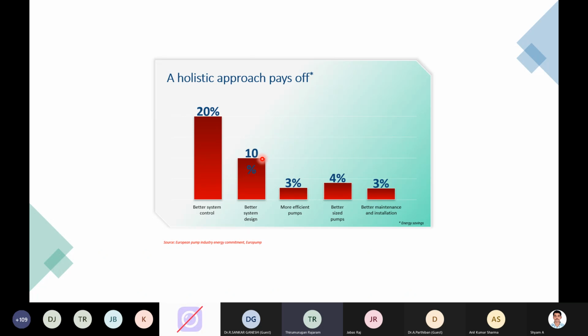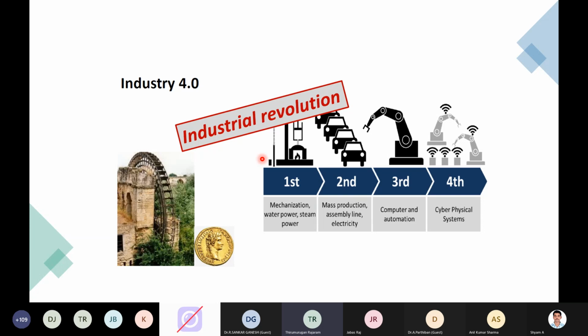So whether you want 4 bar pressure in your line, the pressure transmitter will always sense that and give a signal to the pump so that the scenario will always be maintained. The same thing, if you want a delta T of 5 degrees in your cooling tower, you can have a temperature sensor and operate the pumps based upon it. Likewise, all the products can now be linked to better system control options. And this Industry 4.0 revolution also talks about that, because it is getting into many industries. Even power plants already have a lot of automation inside.